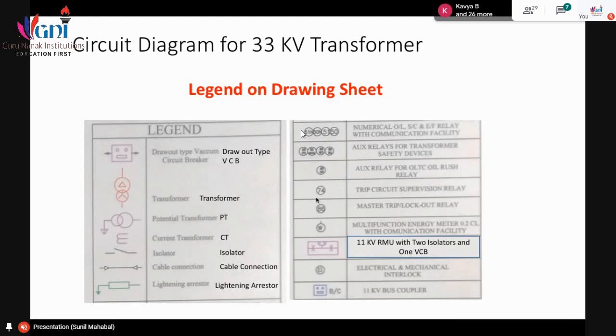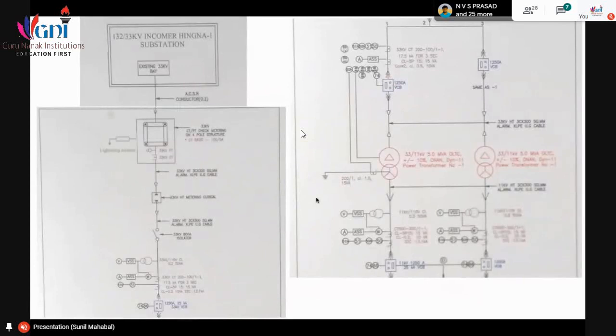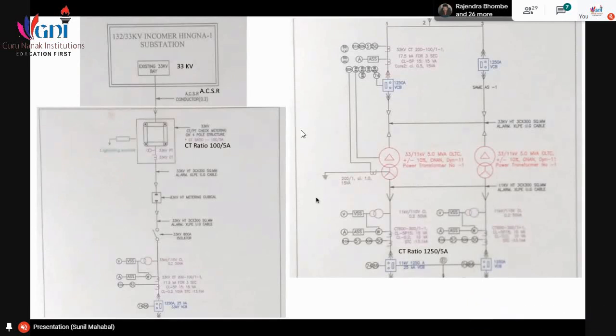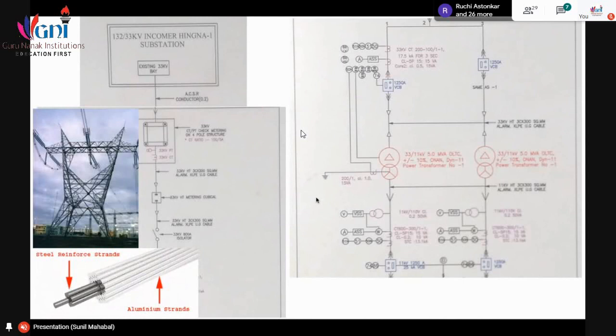Thank you. So in addition to that, this is 11 kV RMU with 2 isolators and 1 VCB. So this is how the circuit looks. It may not be very clear to you on your screen, but for that purpose, I have tagged it also. So this is 33 kV line. Then we receive the power through an ACSR conductor. I hope everybody knows what is ACSR. It is aluminum conductor steel reinforced. So through these wires we receive the supply.